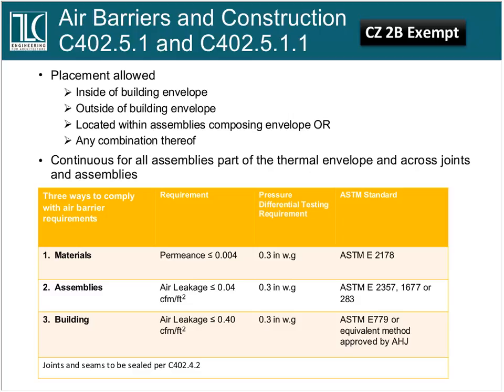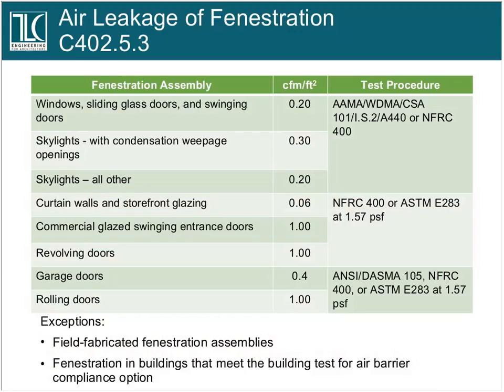Now, this third option is something that we've started to see in residential construction. This is the first time that we've seen it in commercial construction. Imagine, if you will, how difficult it would be to construct a building that's multi-story with big floor plates, lots of floor-to-floor openings like stairwells and windows. It's going to be really hard to do that. Going back to our friends at NFRC, if you don't have NFRC certification on your fenestration, you're going to have to pressure test the building. That's the only way to demonstrate compliance with this mandatory requirement if your windows don't have that NFRC certification, and this includes curtain walls and storefront.